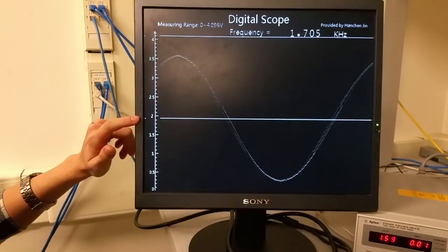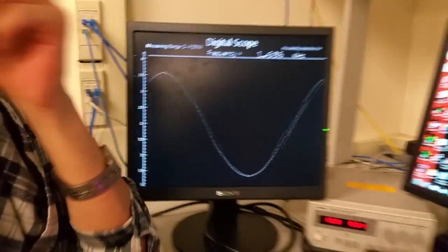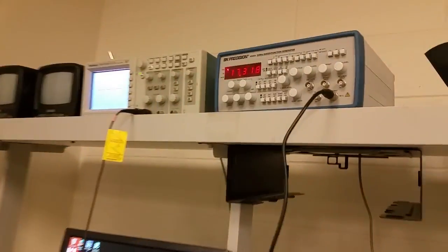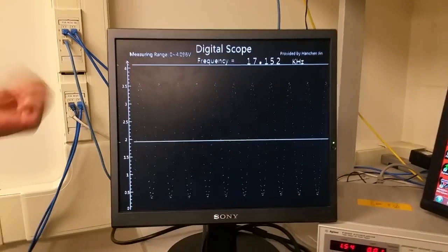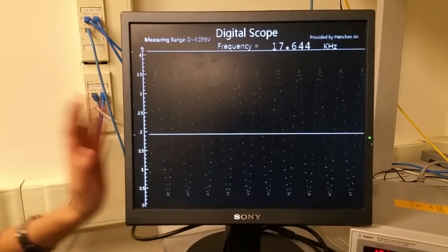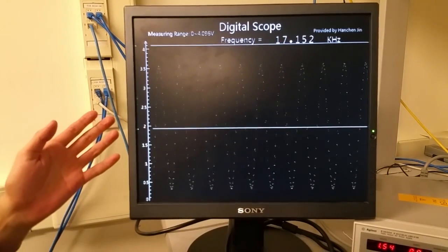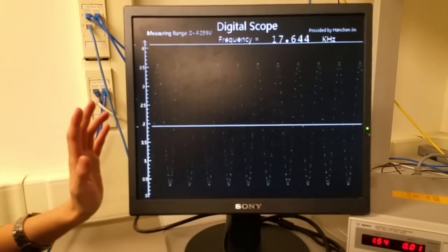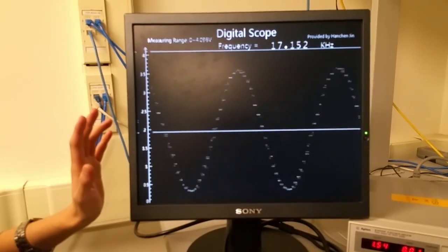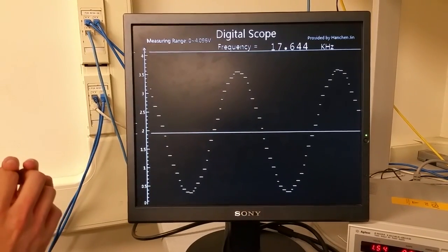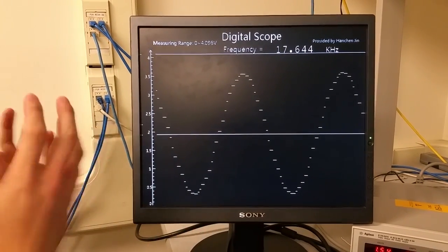Okay. And if you want to measure a frequency with a larger frequency like this, okay. So now you can see that there are too many cycles in one screen, which makes the display a little messy. Mm-hmm. So here you want to change this horizontal position, you can use this function. So the basic idea here is just enlarge one piece of the display and make you get a better waveform.